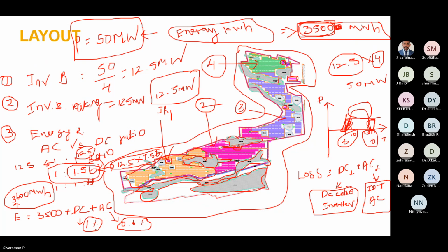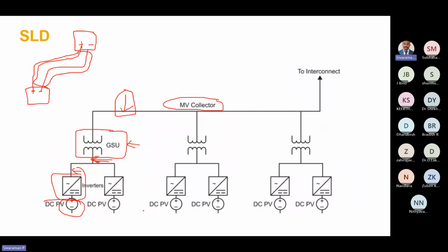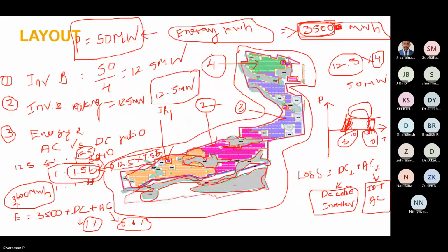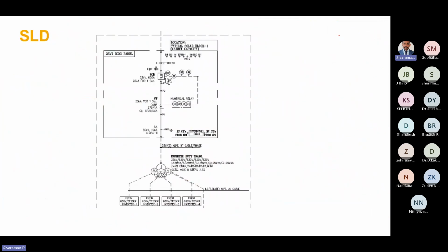Okay, so for total energy, we have to consider the AC losses as well as the DC losses. Some other factor we need to consider is the location of the interconnection. Consider our solar plant is here. Suppose we are going to connect the solar plant to the existing substation. Suppose this plant is in Tamil Nadu, so TNEB is the grid electricity board, and they will already have some substation. At what location do we have to meet this requirement, 50 megawatt, 3500 megawatt hour?